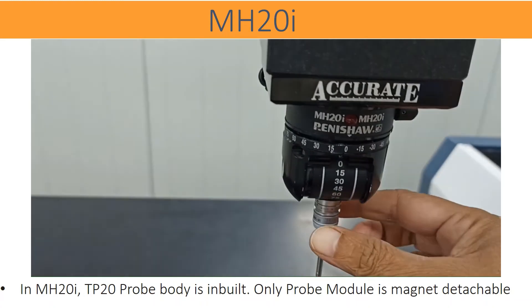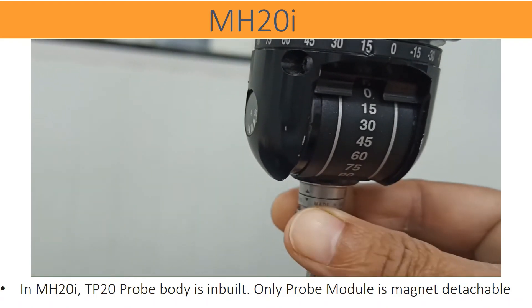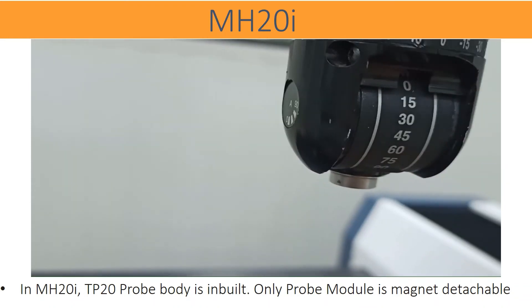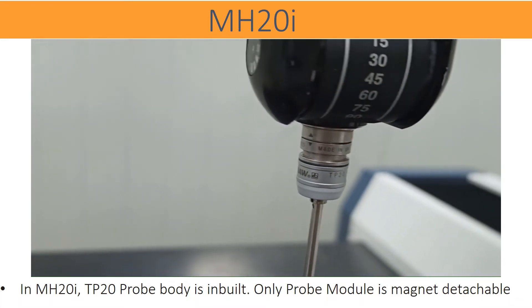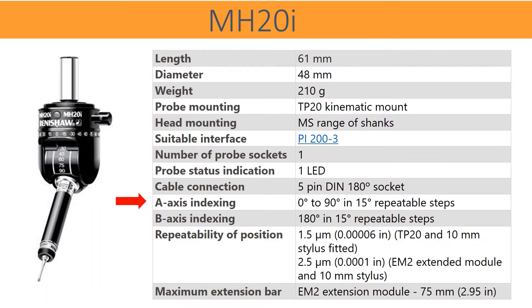MH20i probe head is inbuilt with TP20 probe body. Externally, TP20 cannot be attached. Only the TP20 module is magnetically attached to the probe head. A touch-trigger probe module is possible with an auto-changing rack as well as by hand. A-axis indexing: 0 degrees to 90 degrees in 15-degree repeatable steps. B-axis indexing: ±180 degrees in 15-degree repeatable steps. Repeatability of position: 1.5 µm with TP20 and 10 mm stylus fitted; 2.5 µm with EM2 extended module and 10 mm stylus. Maximum extension bar with EM2 extension module: 75 mm.